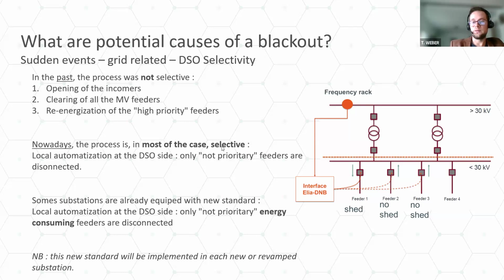Today, in most cases, we have selectivity. It means that we are not opening the incomers anymore, but we only send trip commands to the non-priority feeders. That's very efficient, but it's not so easy in practice. And we are even one step further, because just as Harold explained, with decentralized production, it's complicated to identify which feeders are consuming or producing electricity. And of course, in case of a frequency drop, we only need to do load shedding, not production shedding. Otherwise, the situation is even worse.